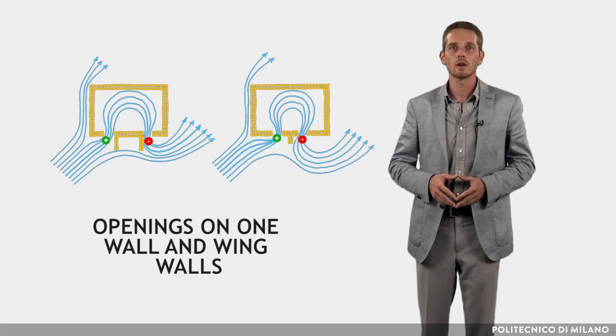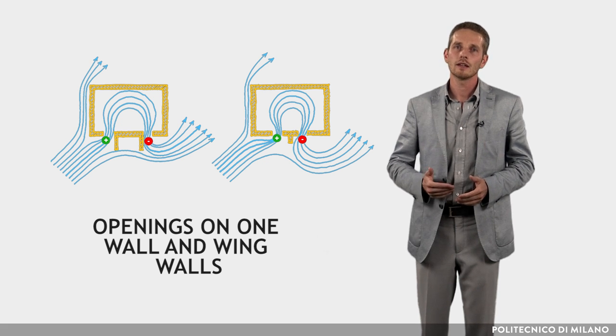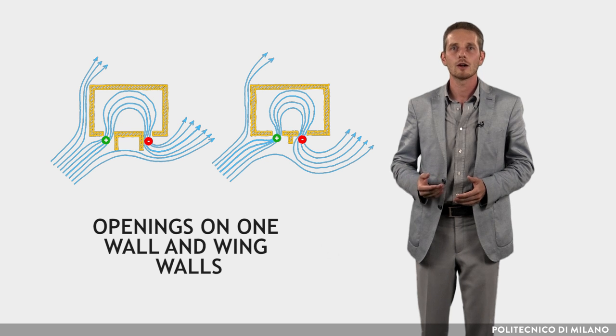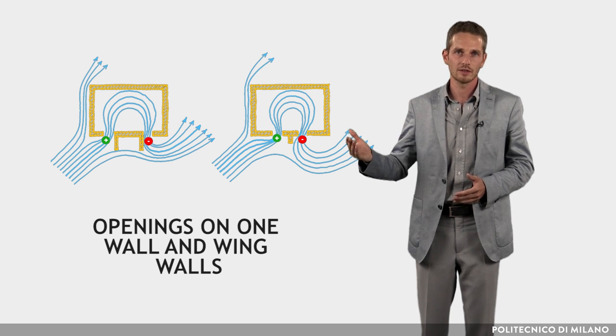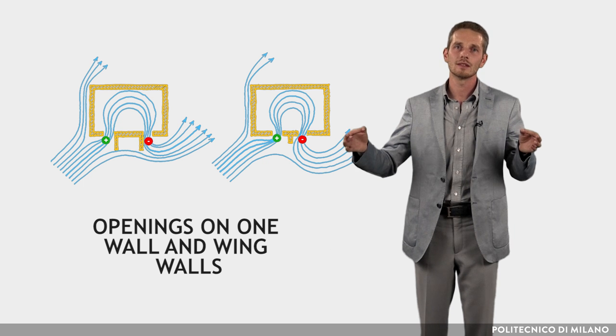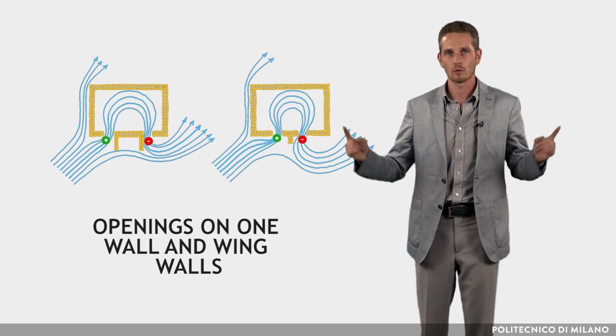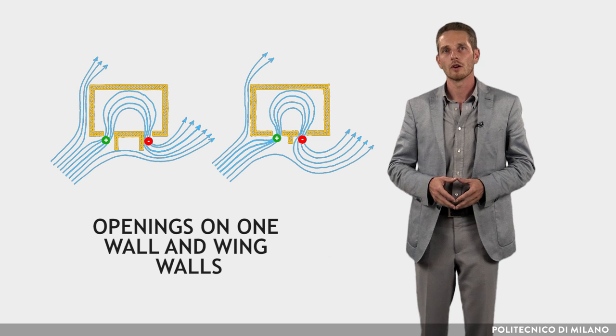In fact, if the window is on the windward side, the available wind velocity is about 10% of the outdoor velocity at points up to a distance one-sixth of the room width. Beyond this, the velocity decreases rapidly.